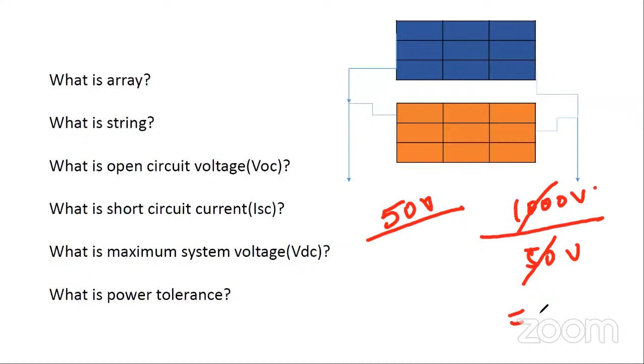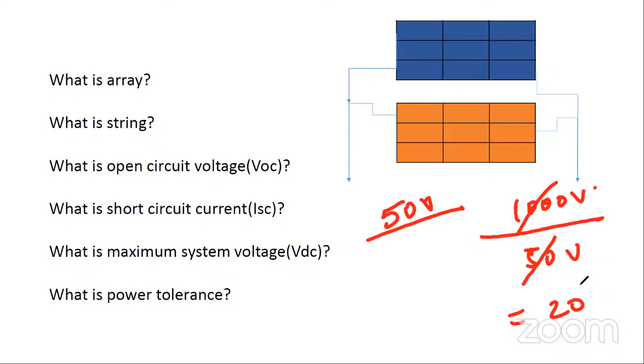In series, if you connect 21 panels, the open circuit voltage will exceed, and if you put it in the circuit, the cable will burn off, because the maximum permissible voltage on the module is 1000 volt. So one should not exceed more than that. In the design, we consider the factor of safety, and we'll be loading only 75 to 85% of the system. The remaining 15 to 20% is always taken as a cushion or factor of safety for future purposes, and also for the safety of the system.